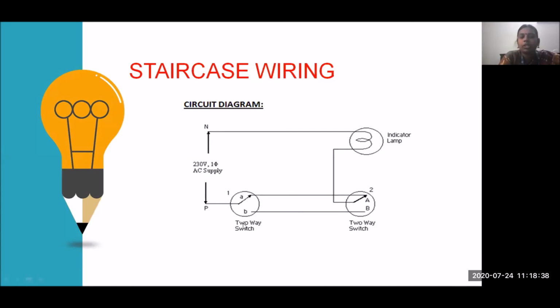Usually switch 1 is kept at the bottom of the staircase and switch 2 is kept at the top. You connect the top point of the first two-way switch to the top point of the second two-way switch, and similarly the bottom point of the first to the bottom point of the second. The middle of the first two-way switch is connected to the phase, and the middle of the second two-way switch is connected to one point of the lamp holder, with the other point connected to the neutral.